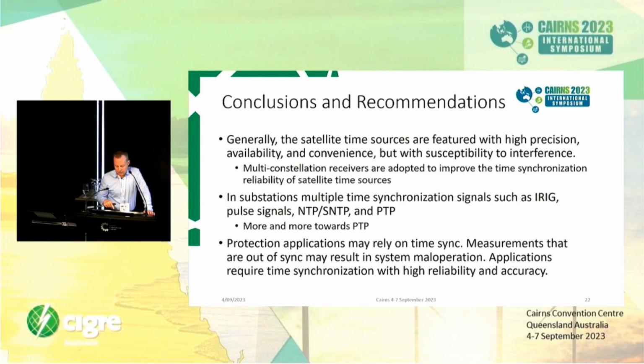Protection system applications may rely on synchronization. Yes, at least modern ones do, and that makes it critical. If the timing is lost, it's not only affecting logs or measurement data, it will also affect operations. For protection relays, it depends on the configuration, but most likely they go into some kind of fault mode in that moment, where differential protection just doesn't work because it doesn't know the timing, or it has some kind of backup to handle it.